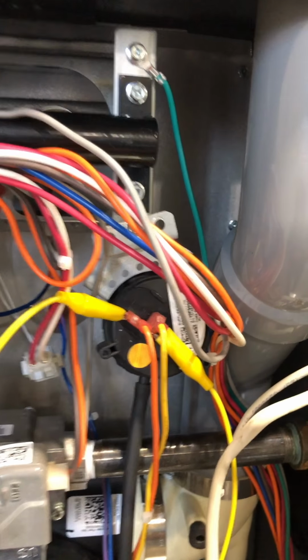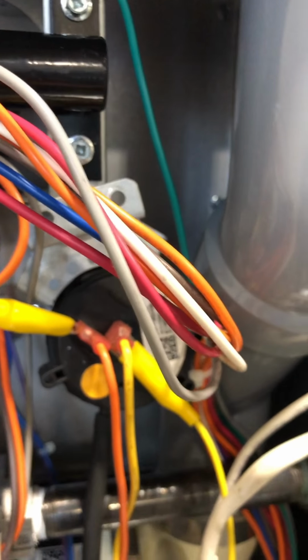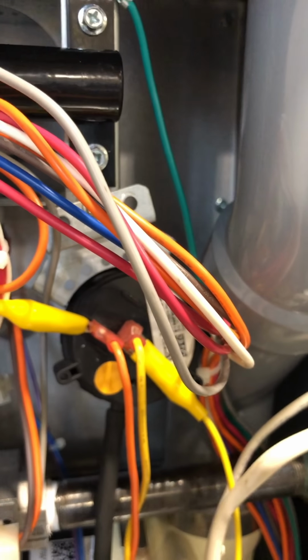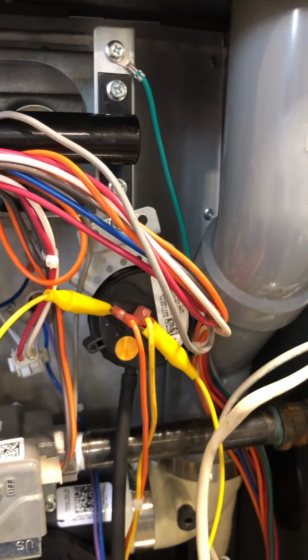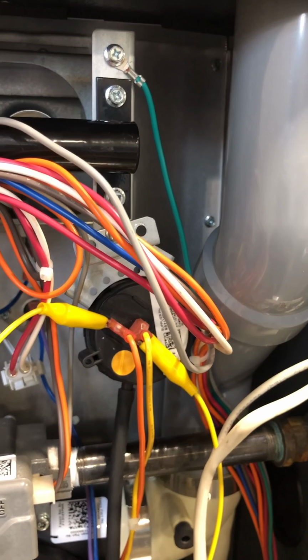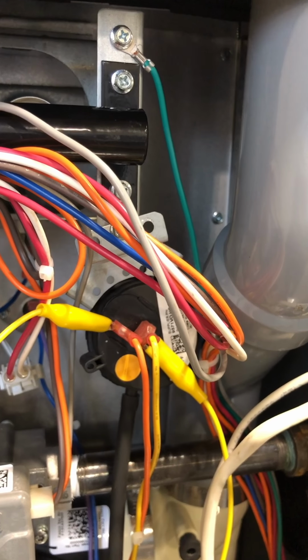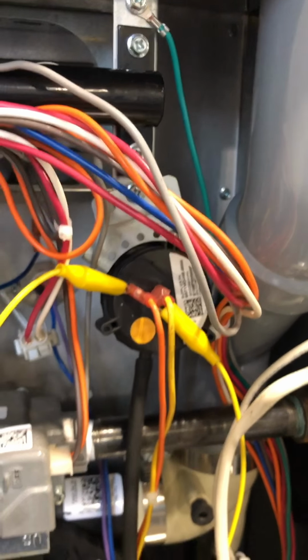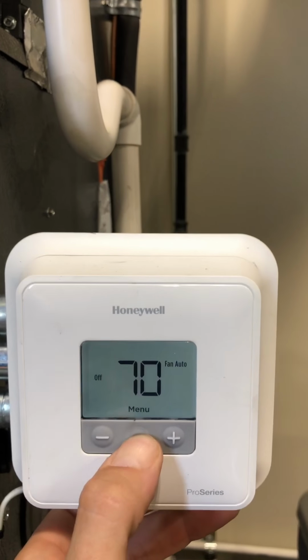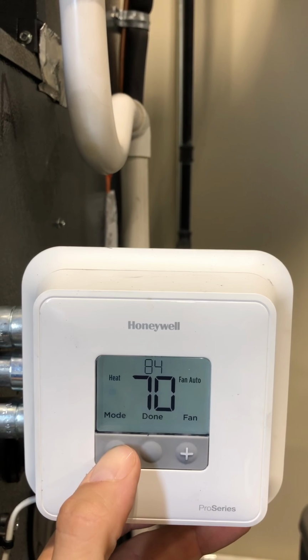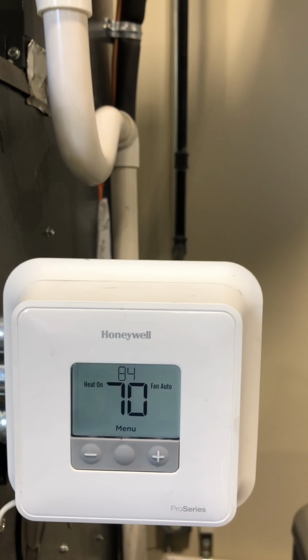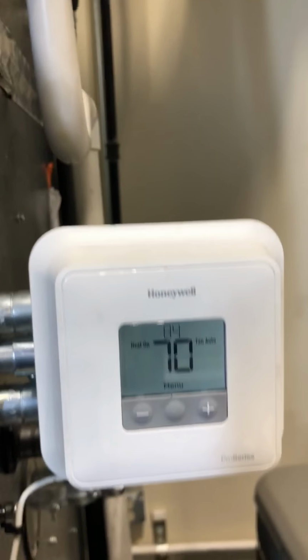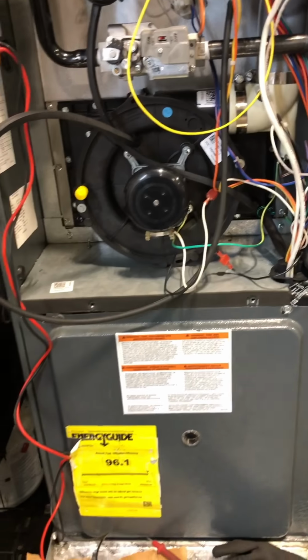So let's test it out. Right now I got the jumper wires on there. So basically what I'm doing is I'm bypassing that switch. The board is going to think that that switch is closed right at the start. I'm just jumping the 24 volts from one terminal right to the other as if the switch was closed. Let's see what happens. Call for heat. No inducer motor, but the blower motor started up.